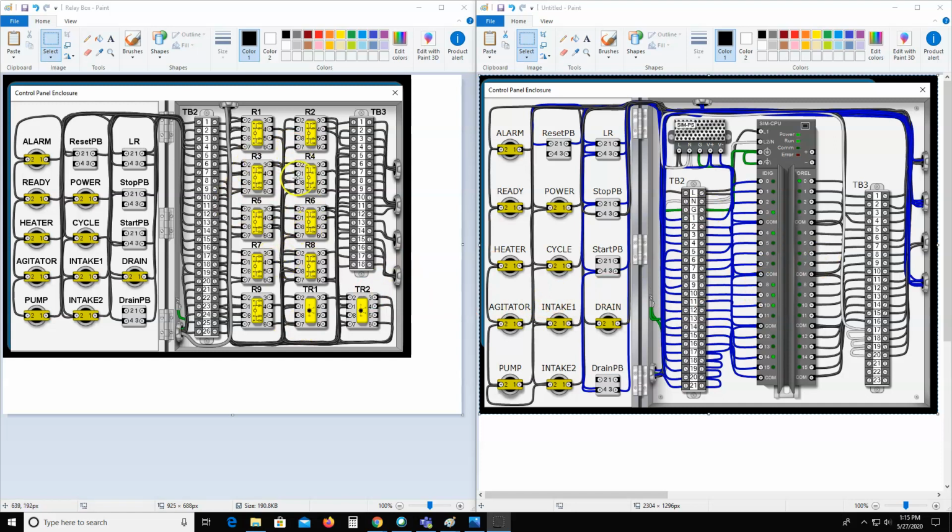You add up the cost of all these relays, the complexity of the wiring, and the complexity of the troubleshooting, plus the fact that you eliminate a couple of these timer relays, because PLCs have their own internal timers as well. You just get a nicer setup, and easier to troubleshoot, in my opinion, and you save yourself a lot of time in build as well, because you can see this would probably be easier to wire and build than its relay counterpart.